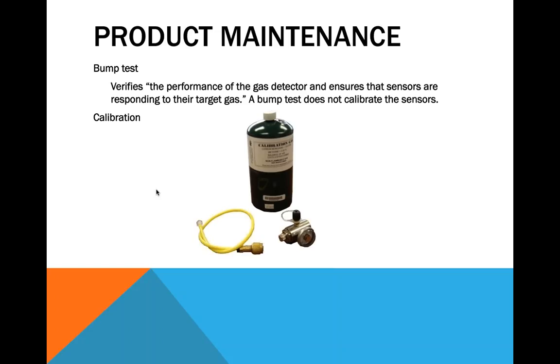Calibration is a different factor that's done generally with a certified container of calibration gas, a regulator to provide the correct flow rate of the gas, and a hose and a fitting such that they fit all together with the product you have. We provide calibration, but we also provide the calibration kits if people are interested in acquiring those to do their own maintenance.